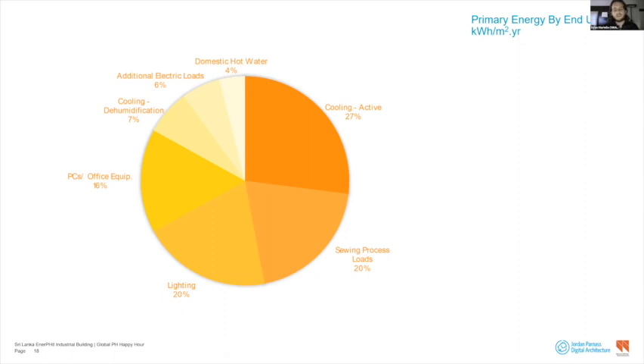One of the things we looked at was quite literally how often the workers were pressing the foot pedals on the sewing machines. We did a sampling - for 2 minutes, how many times they stepped on the foot pedal, for like 15, 20 seconds. That was the level of research that went into quantifying a lot of these loads. But as we'll foreshadow into the future, we were pretty darn close with our estimates. So yeah, sewing process loads are a huge chunk.